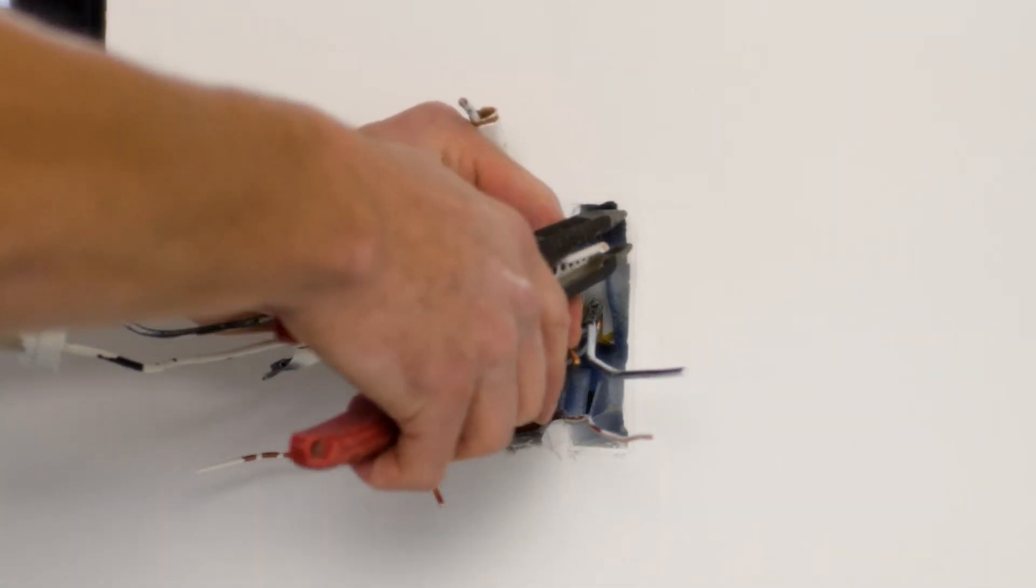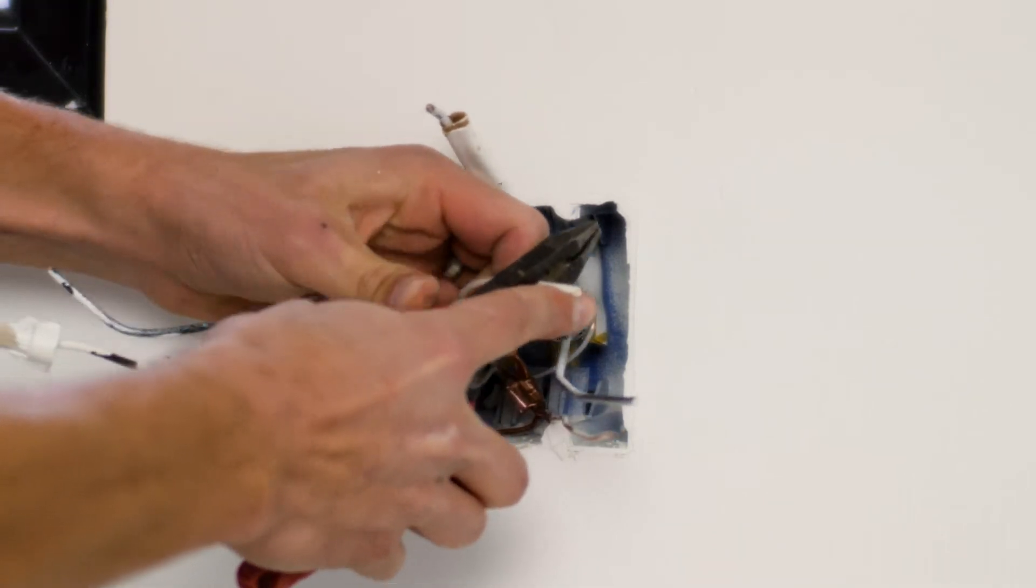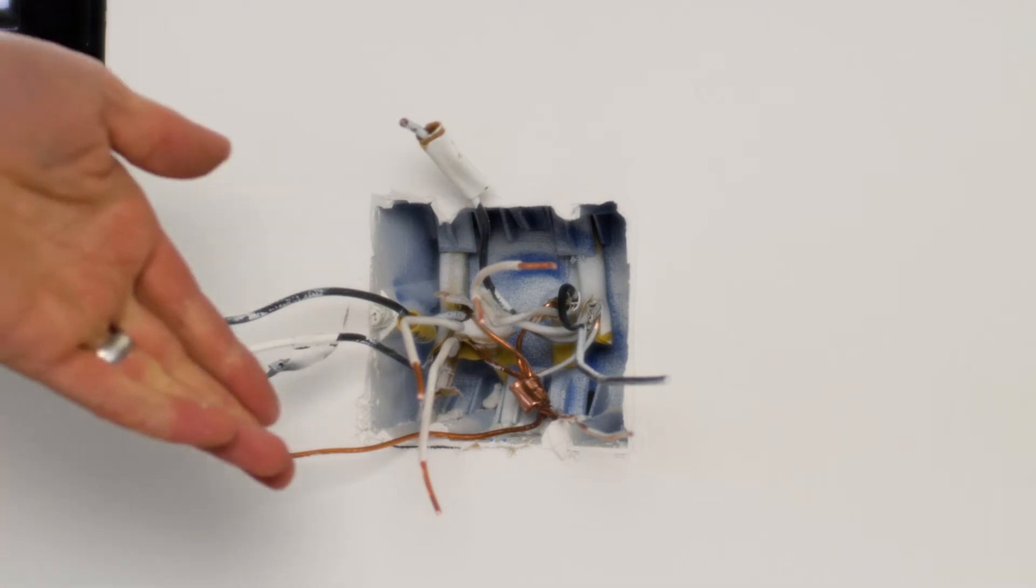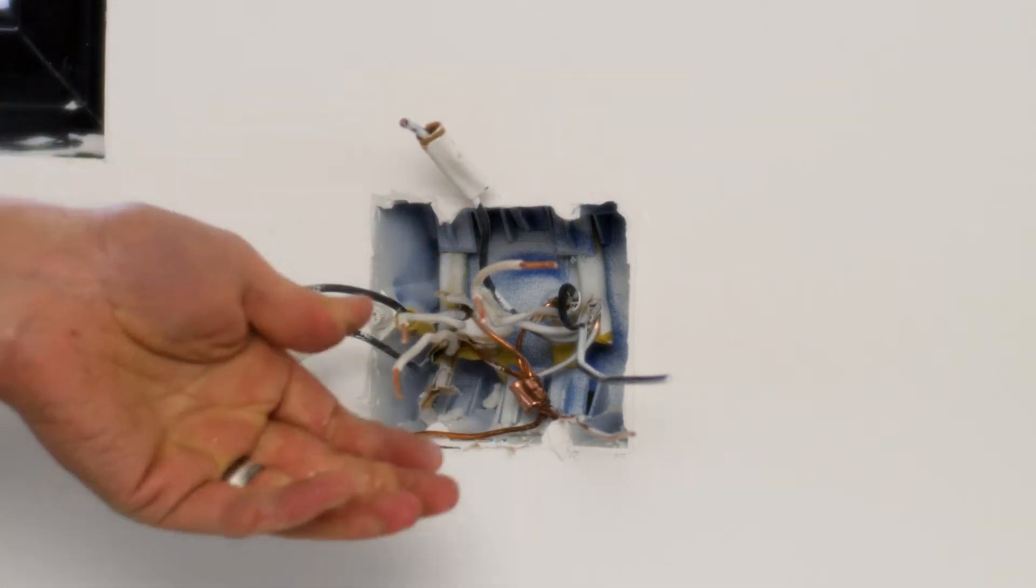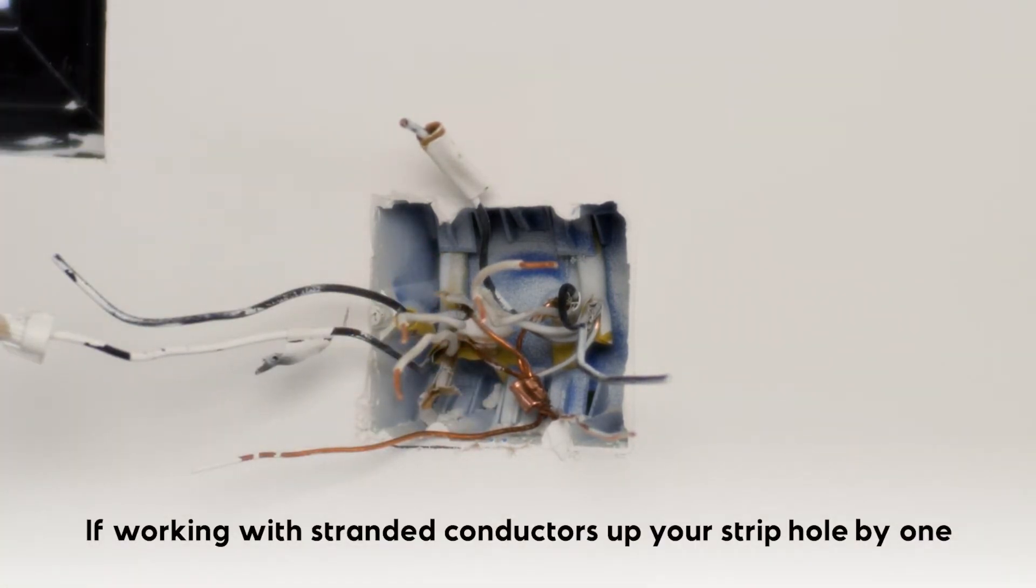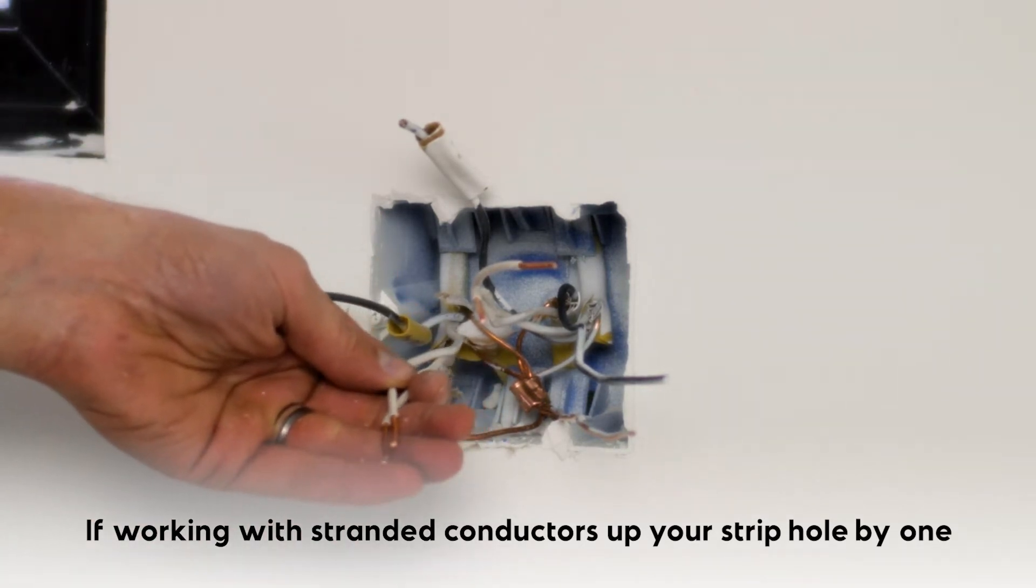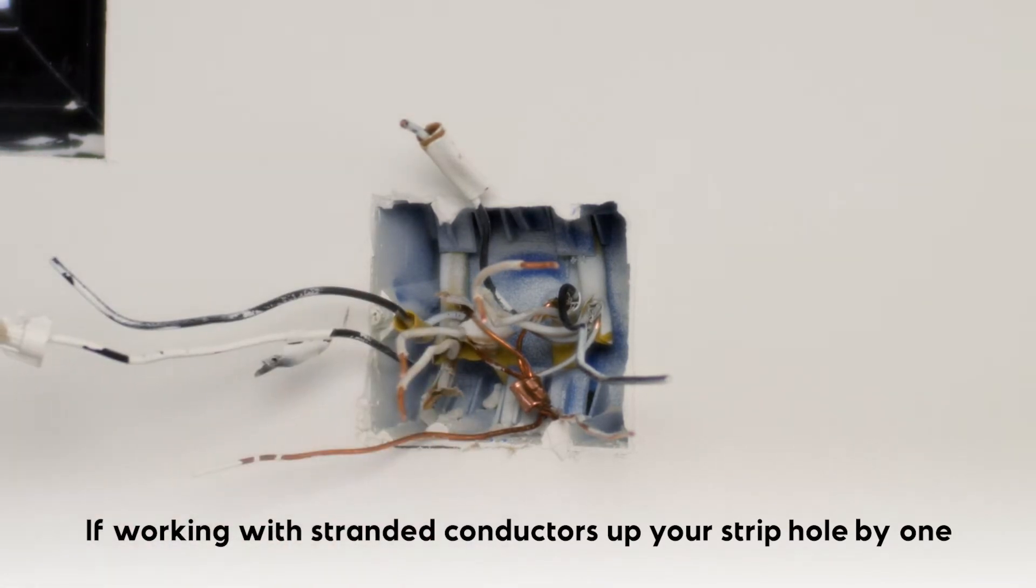It's unlikely in a residence, but in a lot of other circumstances it's quite possible that you'd be working with stranded conductors. In that case, you want to upsize your strip hole by one. For instance, when I'm using number 12 solid, I'm using the number 12 strip hole. But if I'm using number 12 stranded, I'm going to be using my number 10, next size up strip hole based on wire gauge.